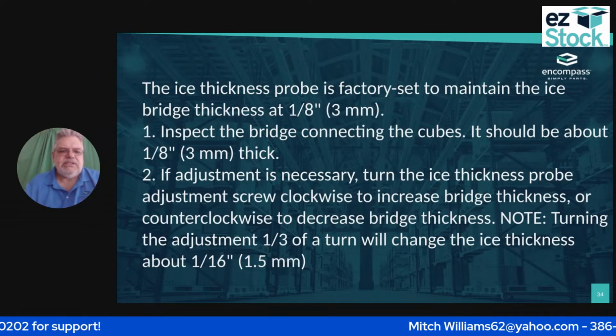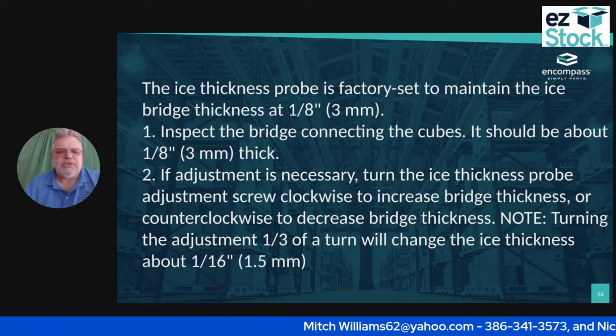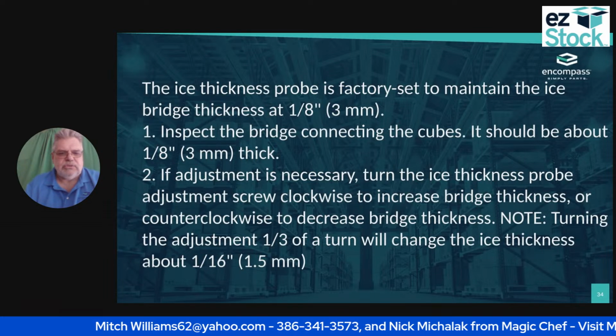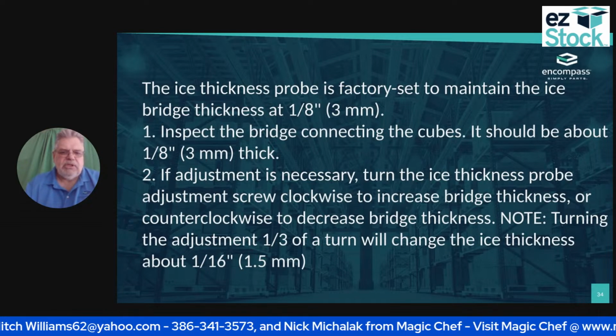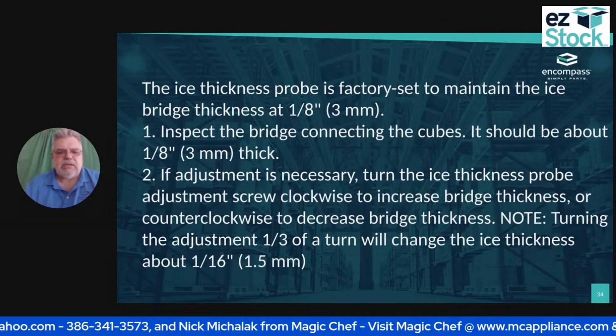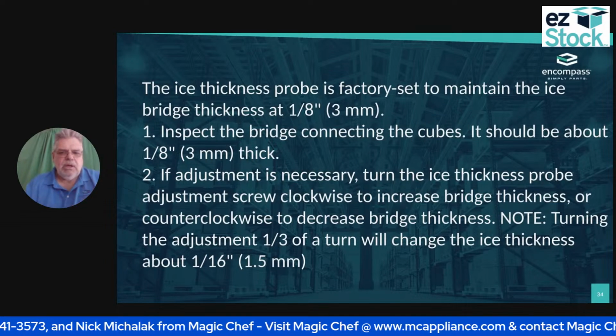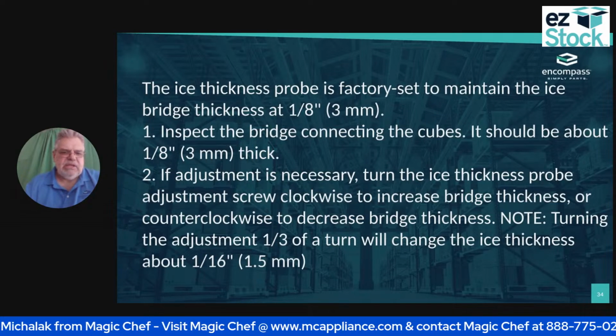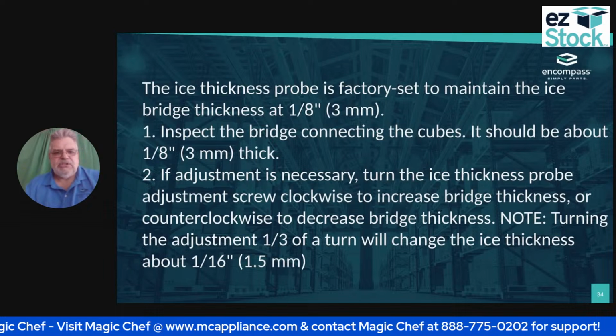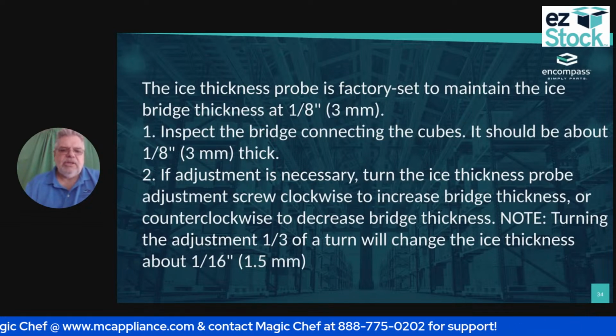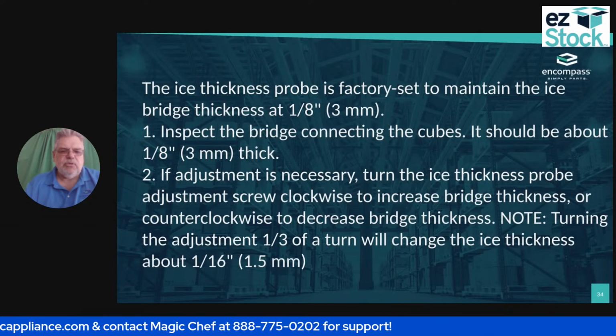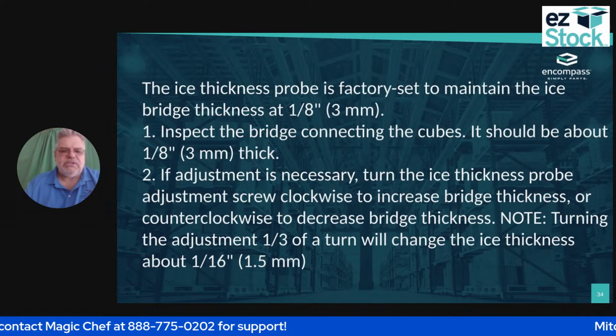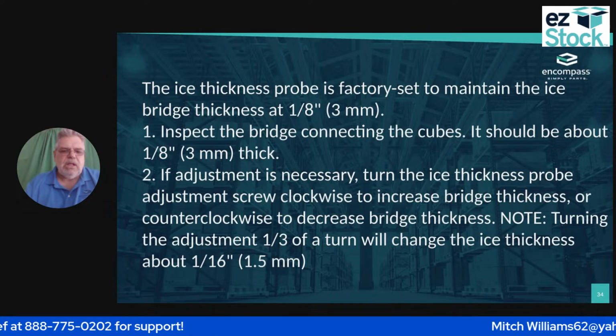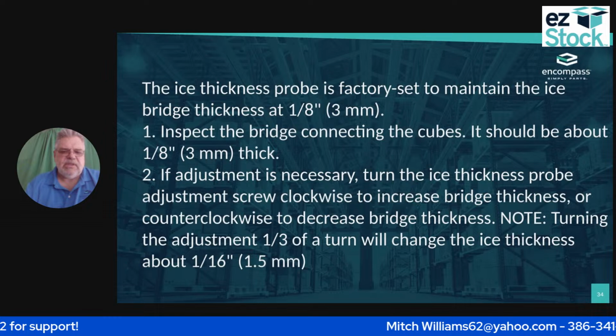Okay. The ice thickness probe is factory preset to the ice bridge thickness of 1/8 of an inch, which is 3 millimeters. I'm going to inspect the bridge connecting the cubes. It should be about 1/8 of an inch. If an adjustment is necessary, turn the ice thickness probe adjustment screw clockwise to increase the bridge thickness or counterclockwise to decrease the bridge thickness.